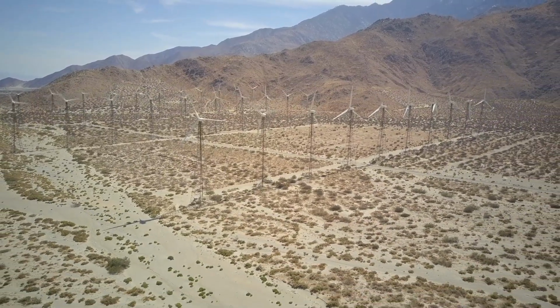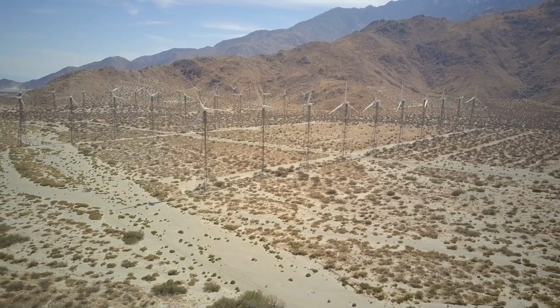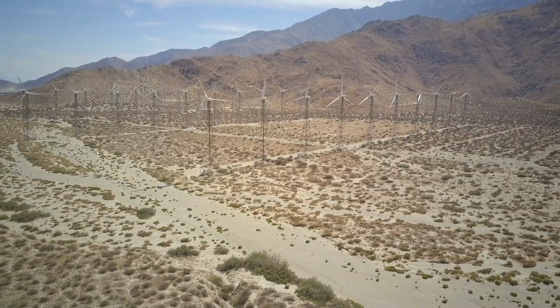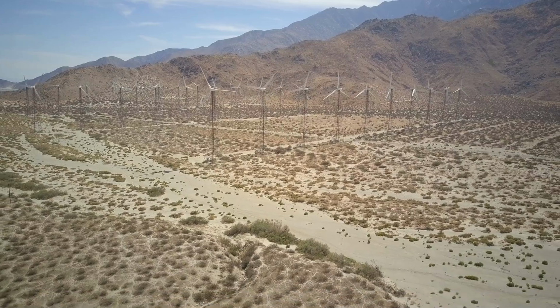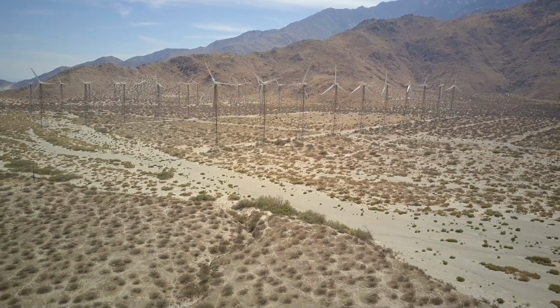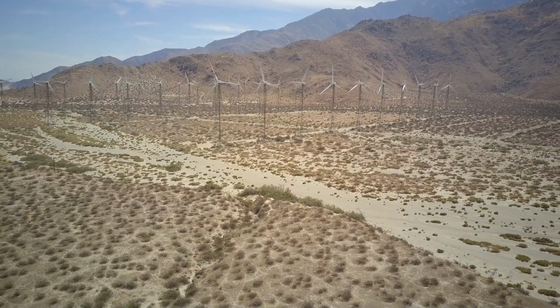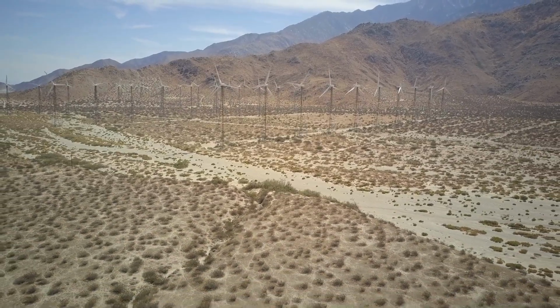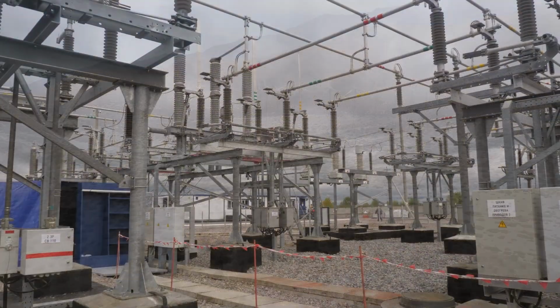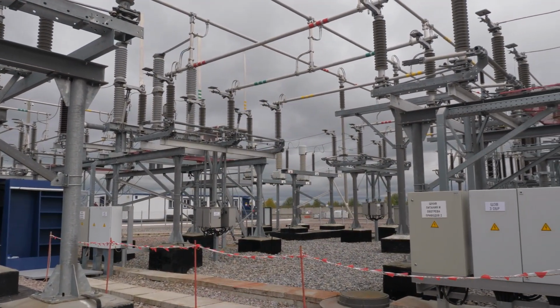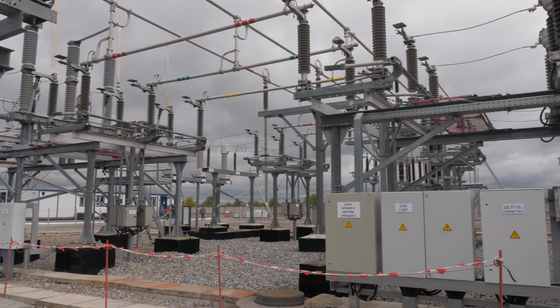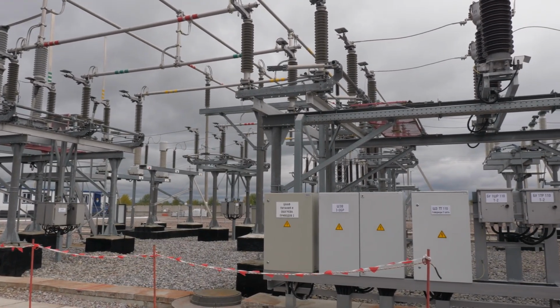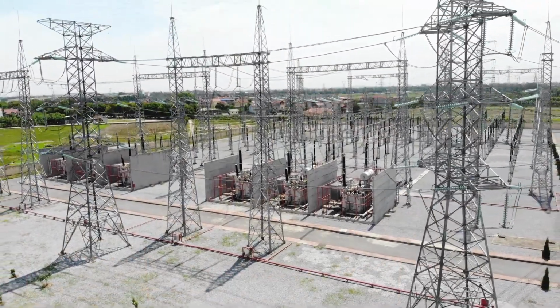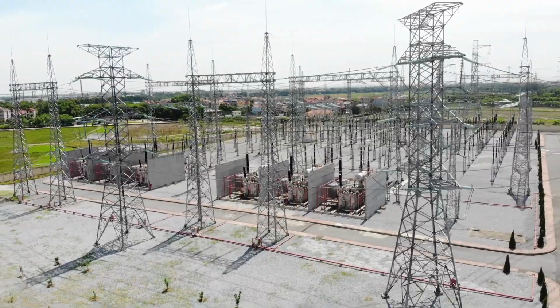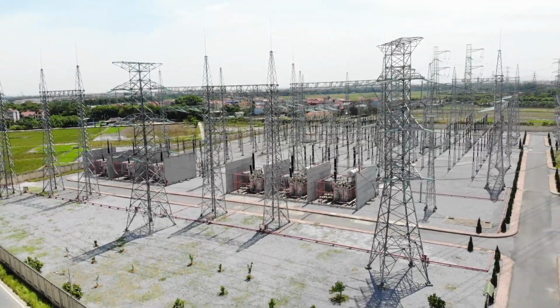The study process exists for a legitimate reason. Connecting a new source of generation to a transmission system changes the flows on every line in the surrounding network. Some of those lines may not have the capacity to absorb the change. Some substations may require upgrades. Some protection systems may need to be reconfigured. The interconnection study is how the grid operator identifies those requirements and assigns their cost to the project requesting connection.